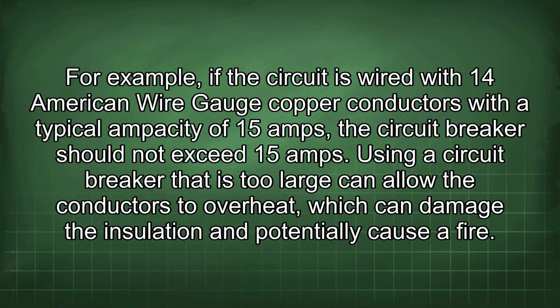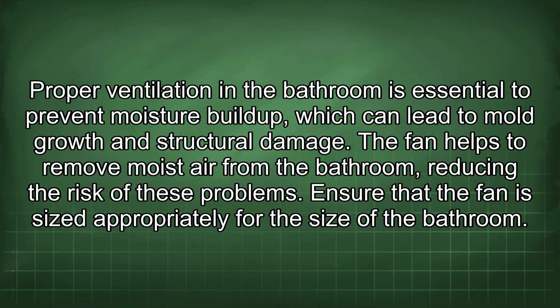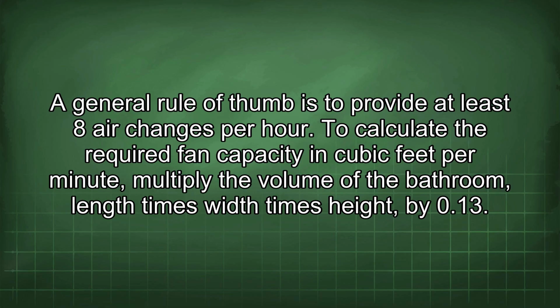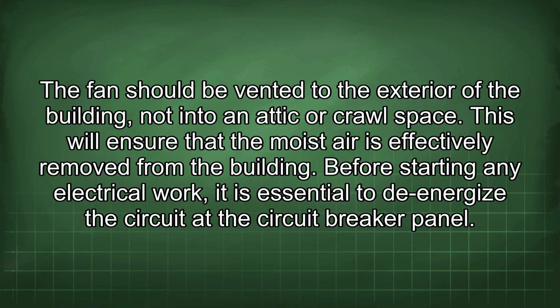Proper ventilation in the bathroom is essential to prevent moisture buildup, which can lead to mold growth and structural damage. The fan helps to remove moist air from the bathroom, reducing the risk of these problems. Ensure that the fan is sized appropriately for the size of the bathroom. A general rule of thumb is to provide at least 8 air changes per hour. To calculate the required fan capacity in cubic feet per minute, multiply the volume of the bathroom, length times width times height, by 0.13. The fan should be vented to the exterior of the building, not into an attic or crawl space. This will ensure that the moist air is effectively removed from the building.